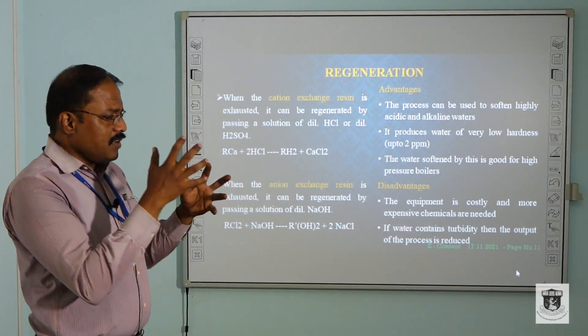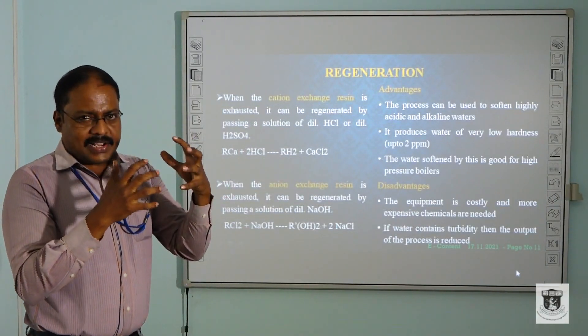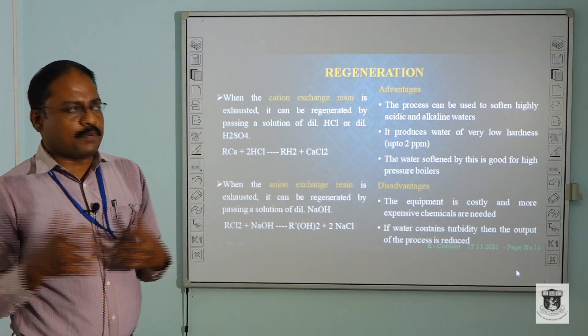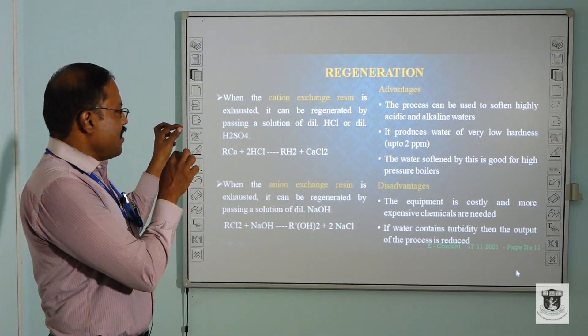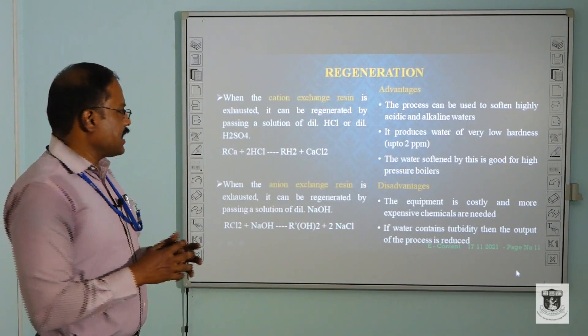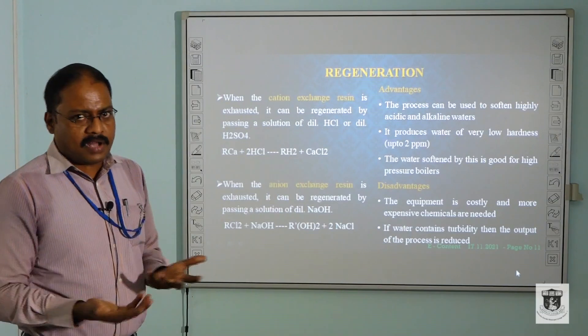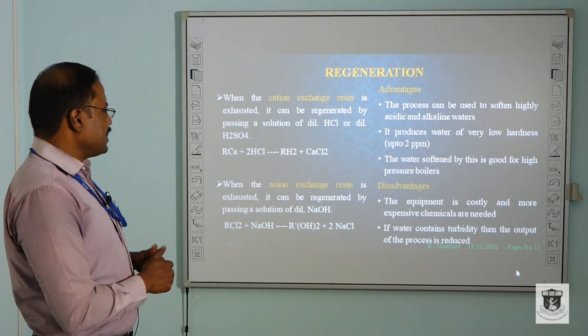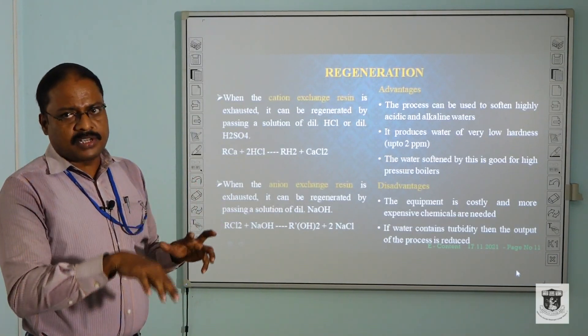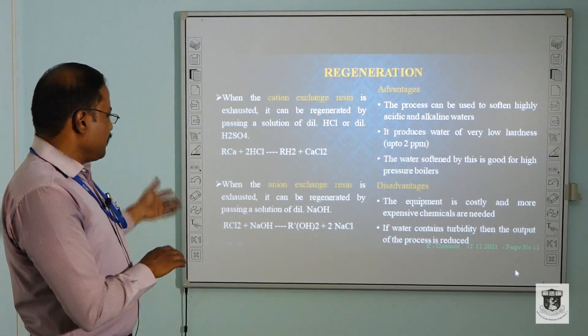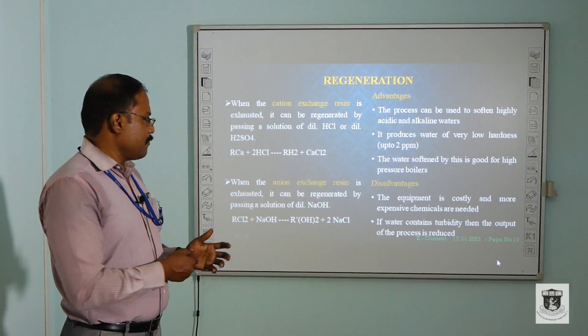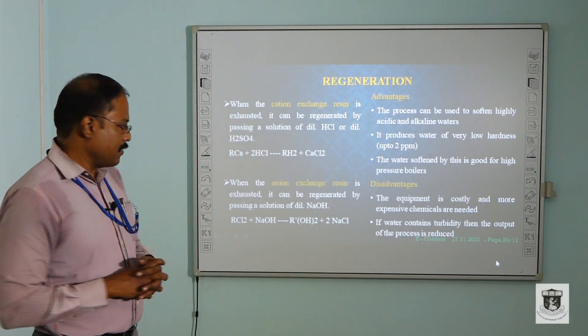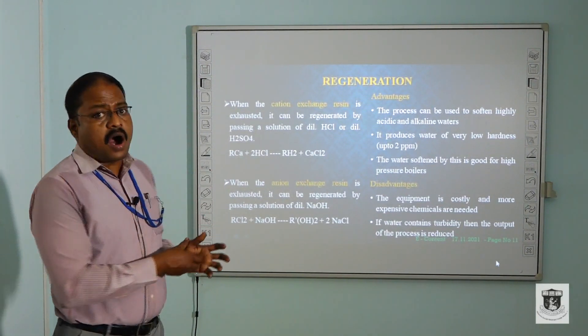Once the bed is exhausted — whether the cation exchange resin or anion exchange resin — we carry out regeneration. The exhausted cation exchange resin can be regenerated by passing a solution of dilute hydrochloric acid or dilute sulphuric acid, which easily converts it back to the original form RH₂. When the anion exchange resin is exhausted, it can be regenerated by passing a solution of dilute sodium hydroxide, which converts it back to R(OH)₂.